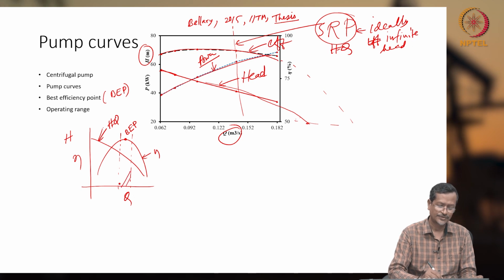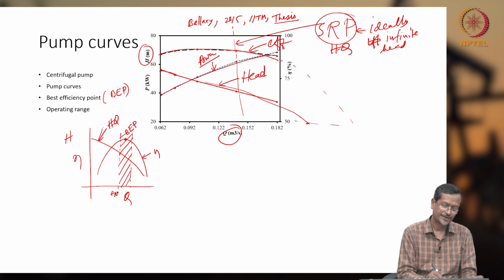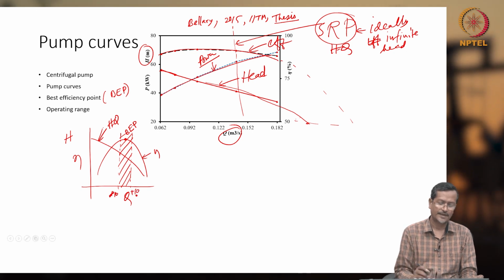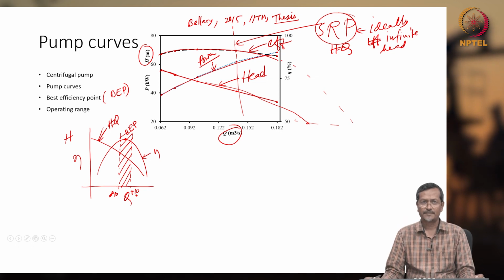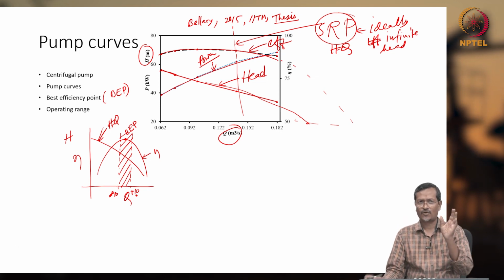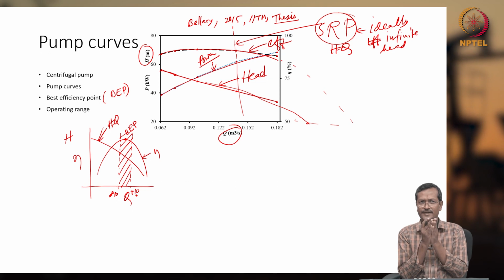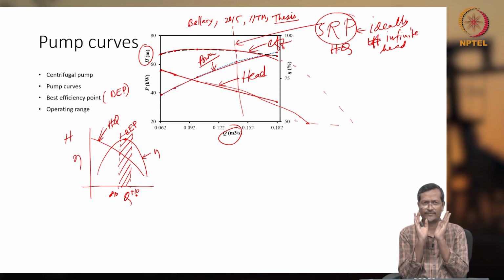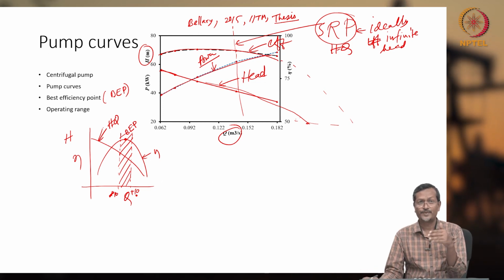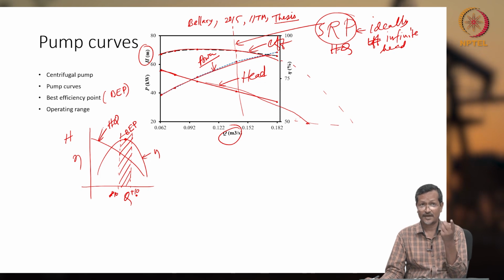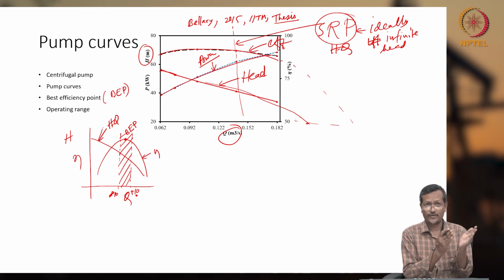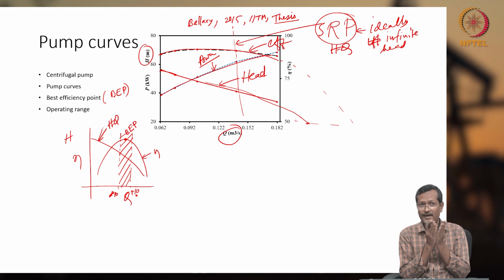Okay. So, this will be your operating range, plus 10, this is minus 10, about 10% plus minus you can make. So, that will be giving the operating range. Within that, if you are running, then your pump will be running in very good condition. It will be consuming less energy because it is highly efficient. But if you are going away, what will happen? It will not give the highest efficiency.